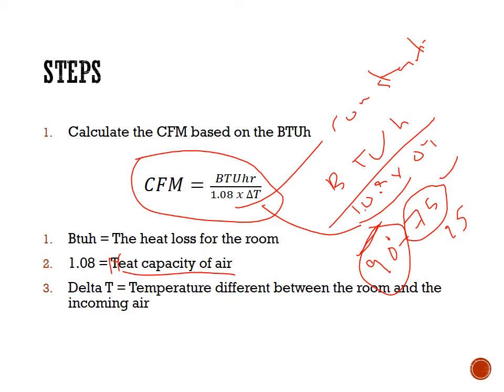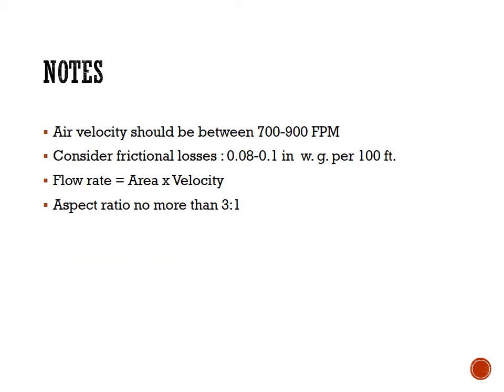Make sure you have a positive number here, and this is how you convert for each room the BTU into CFM. Here are some notes we have to think about when we do sizing for duct. Again, it's very involved work, and it requires some experience, but at least you have the cliff notes here of what you have to do.